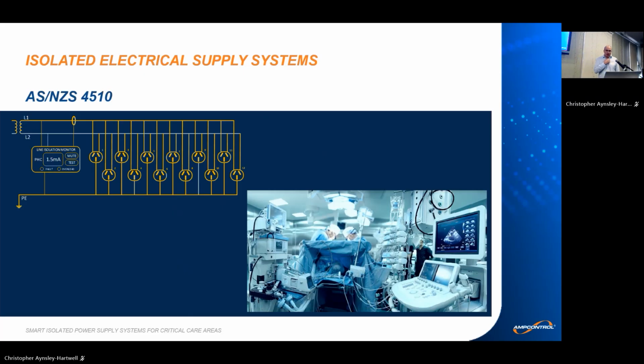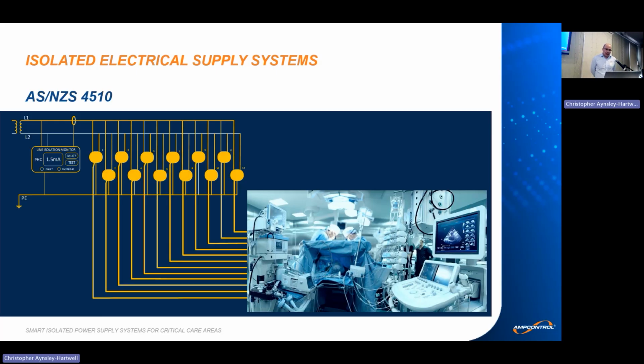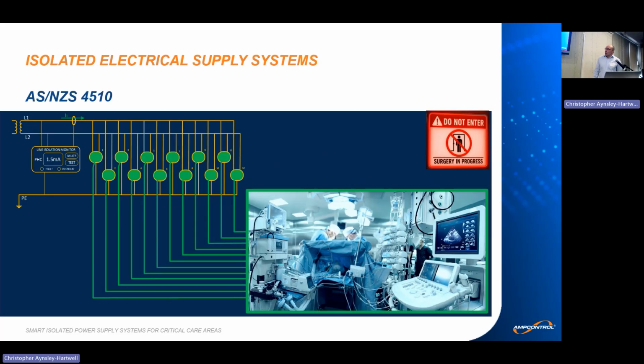Let's use as an example a typical operating room protected by an isolated electrical supply system. One isolated electrical supply system can provide power to up to 12 pieces of medical equipment. And let's imagine a situation where we have a surgical procedure in progress and everything is going well. All 12 pieces of medical equipment are operating normally, and the line isolation monitor monitors the power distribution system for potential hazards and faults. And the surgical procedure is progressing well until suddenly a prospective hazard current alarm is triggered by the line isolation monitor. And this is where the challenge begins. The line isolation monitor tells us that there is a problem in the operating room, but what it doesn't tell us is where the fault is.